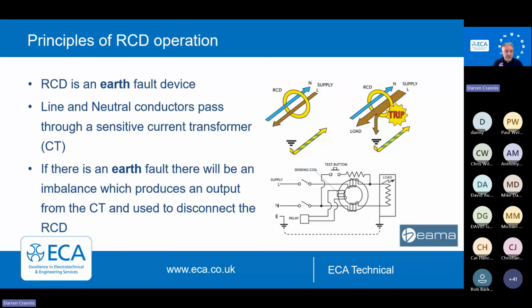We moved away from voltage operated to current operated. And they're really simple in how they work. All they do is they look for an imbalance through a coil of what goes in must come out. So it's the same as counting people in and out of a nightclub. They're counting you in, counting you out. They've got to tally. And it's a very sensitive little current transformer.